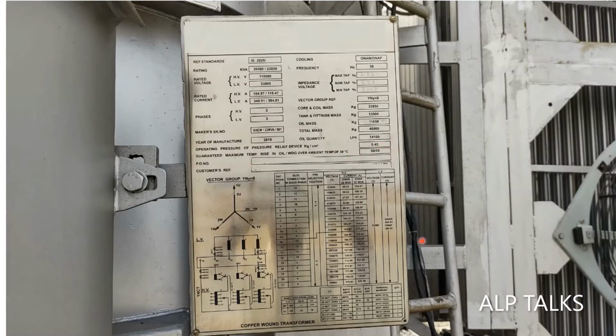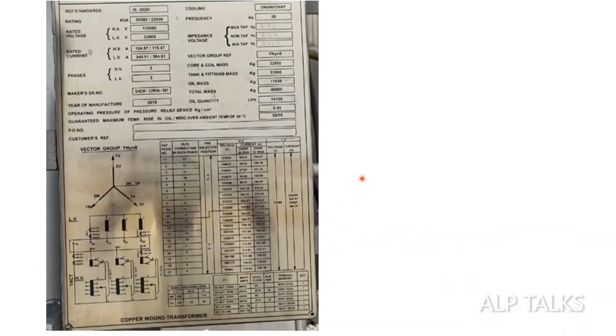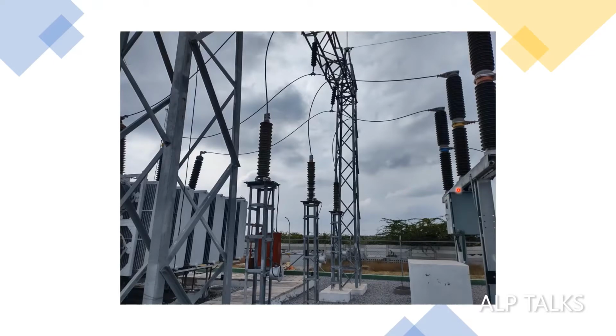This is the connection diagram. We have CT also, and the CT details we can see here. This is also a similar thing, I think. So this is the substation. After generation of power from solar panels, it goes to the string combiner, inverter, then to the transformer, then to the ring main unit, and then to the power transformer. This power transformer is stepping up from 33 kV to 110 kV. We can see the step up arrangement here.